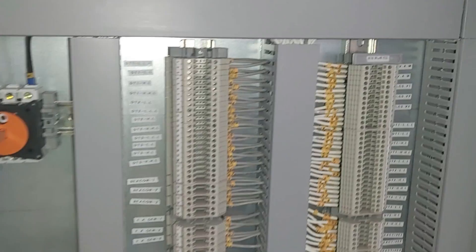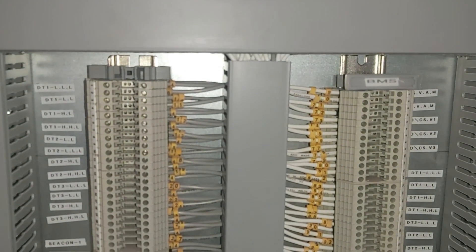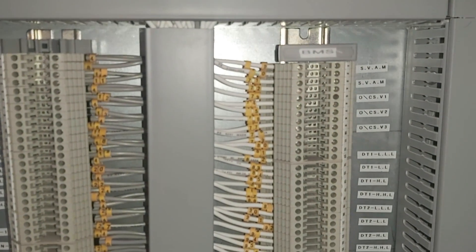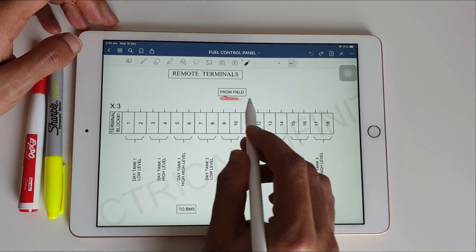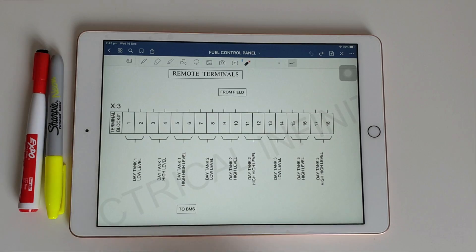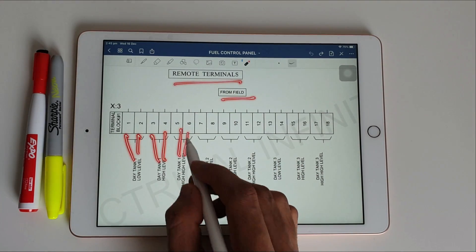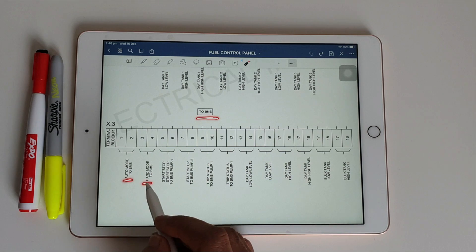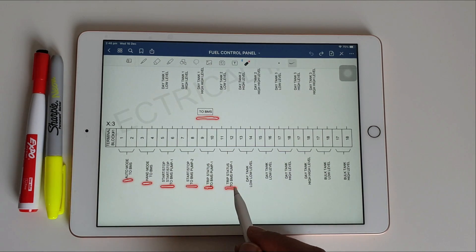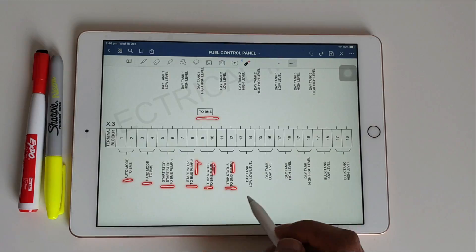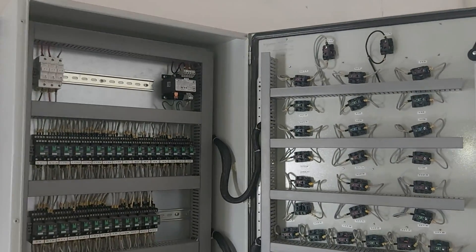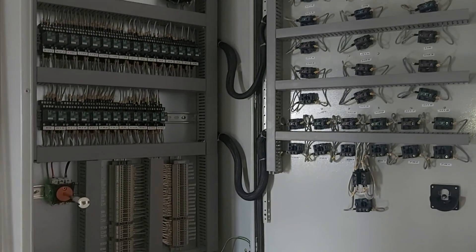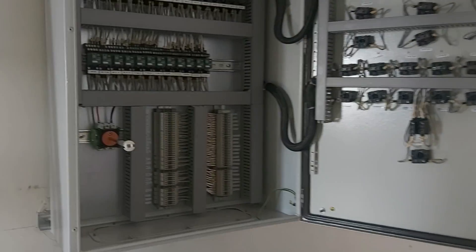Finally, this panel has two terminal blocks. One terminal block is from the field, receiving values from the various tank sensors so the panel can operate depending on tank levels. The second terminal block connects to BMS, sending the status of the pumps to the building management system. That completes the explanation of this panel. Hope you liked this video — don't forget to subscribe to Electrical Infinity. Thanks for watching, take care.